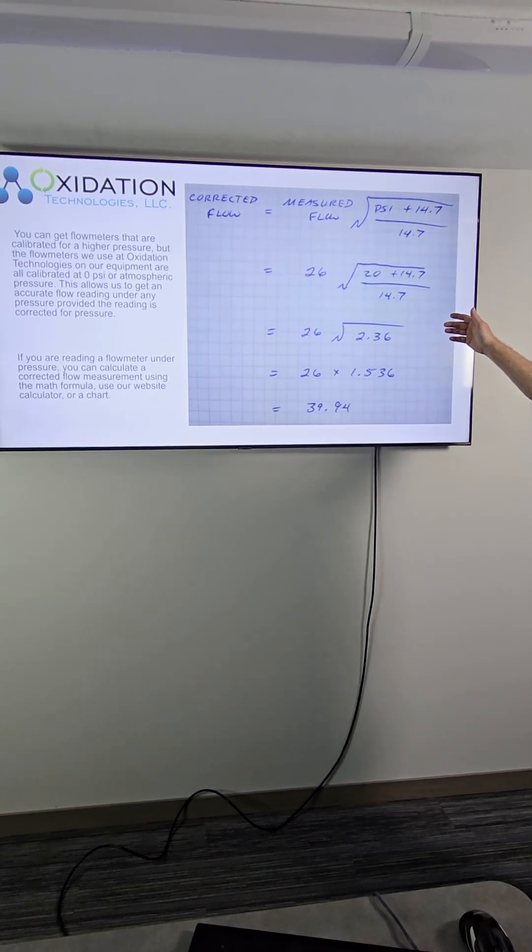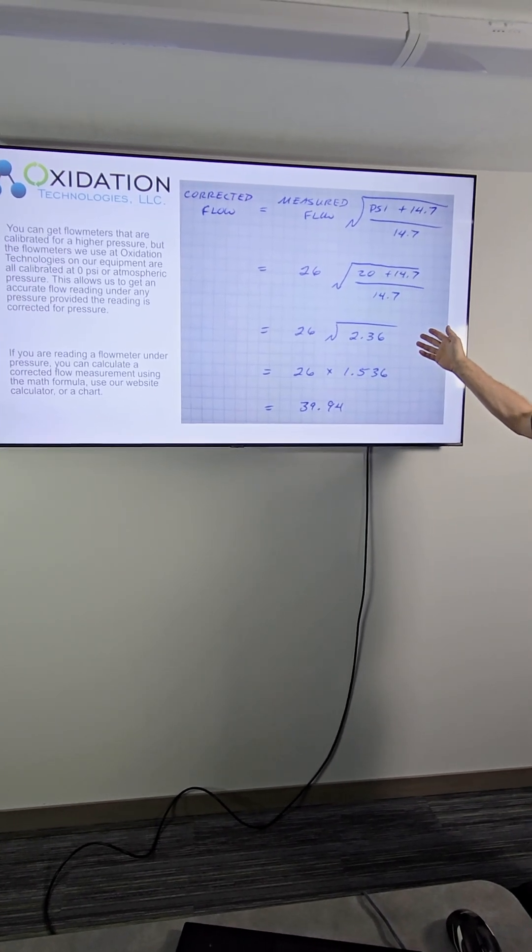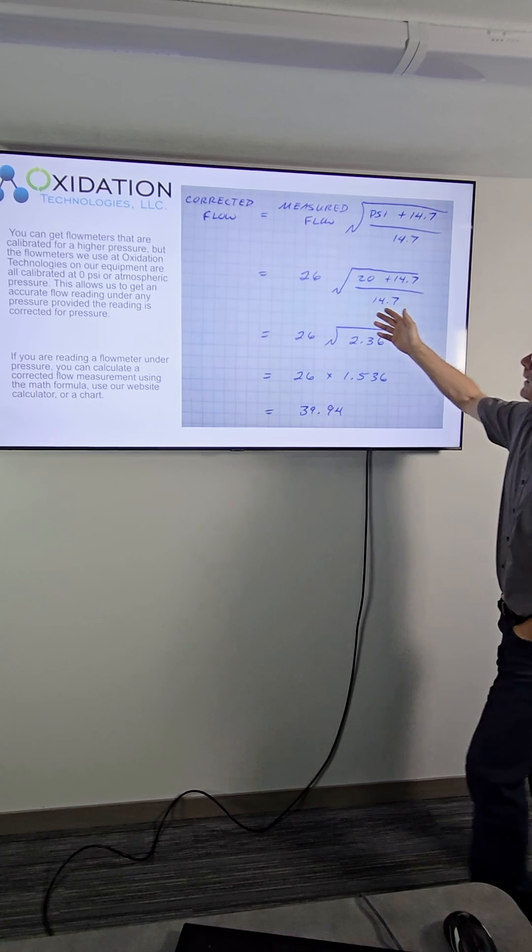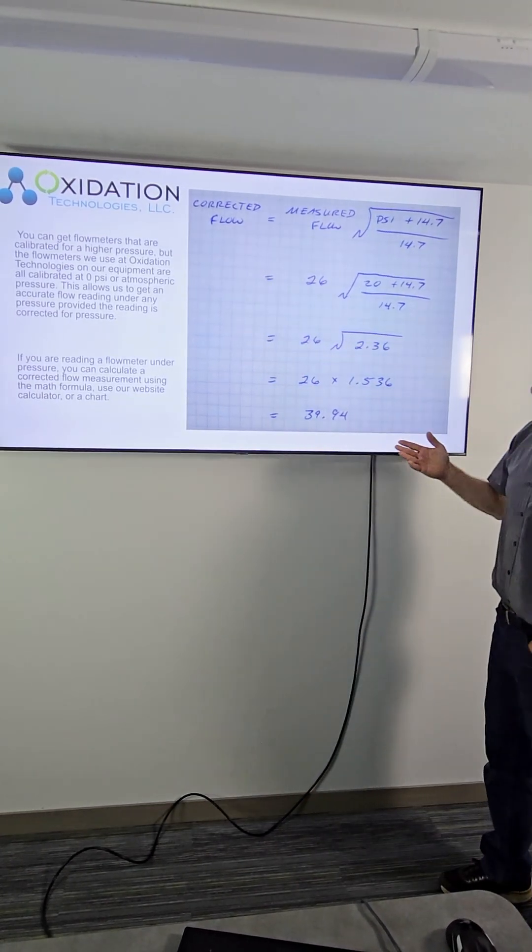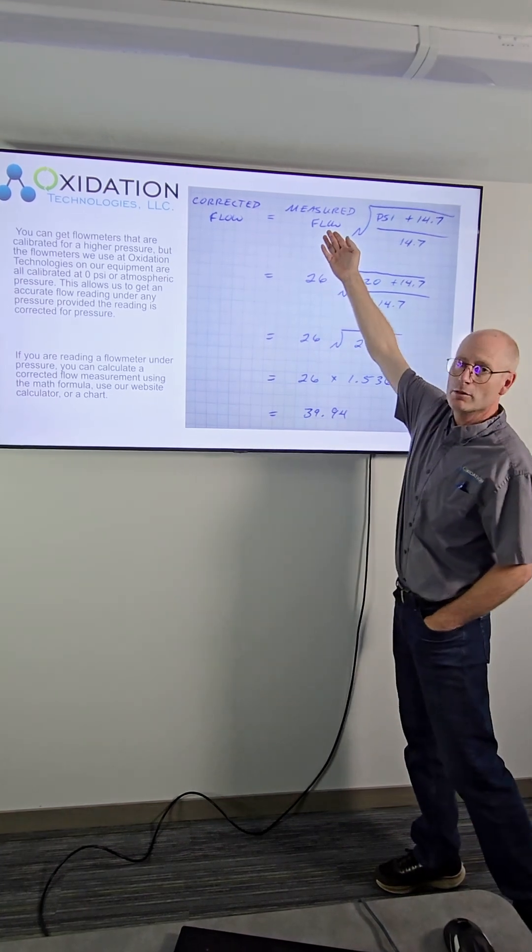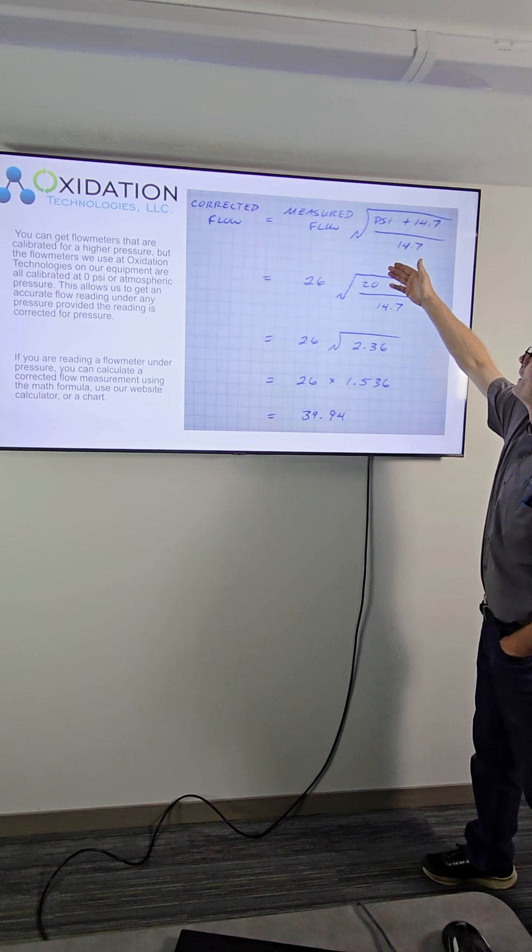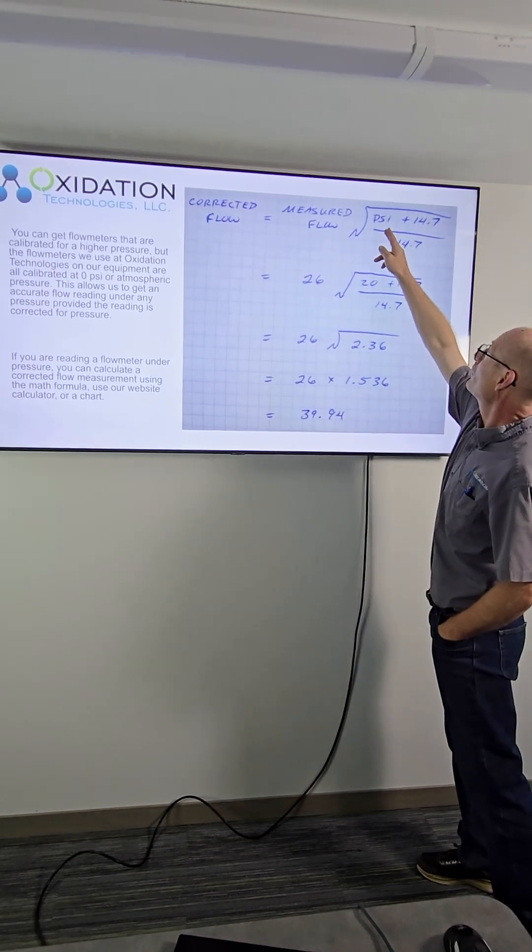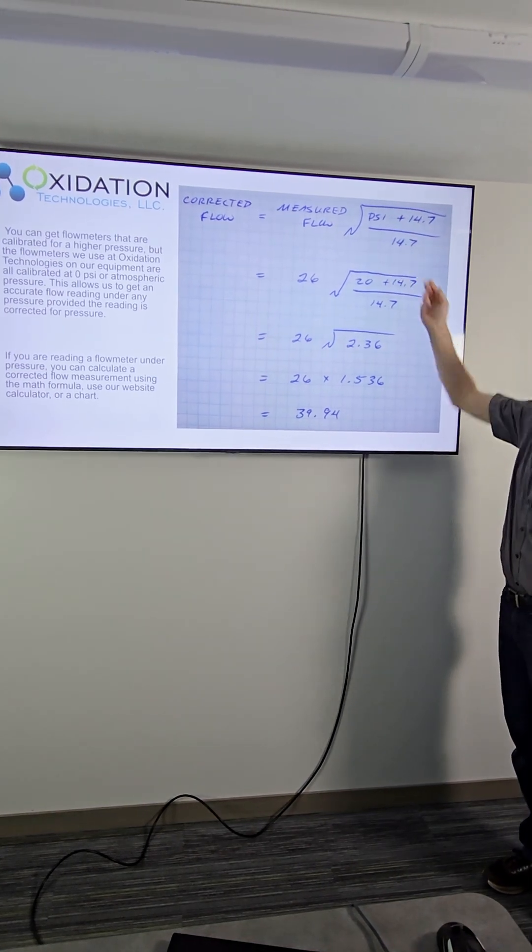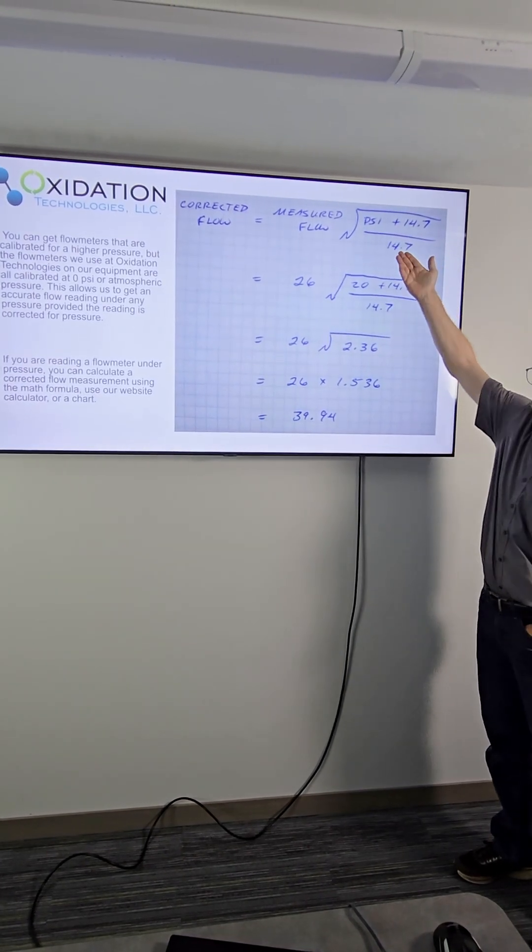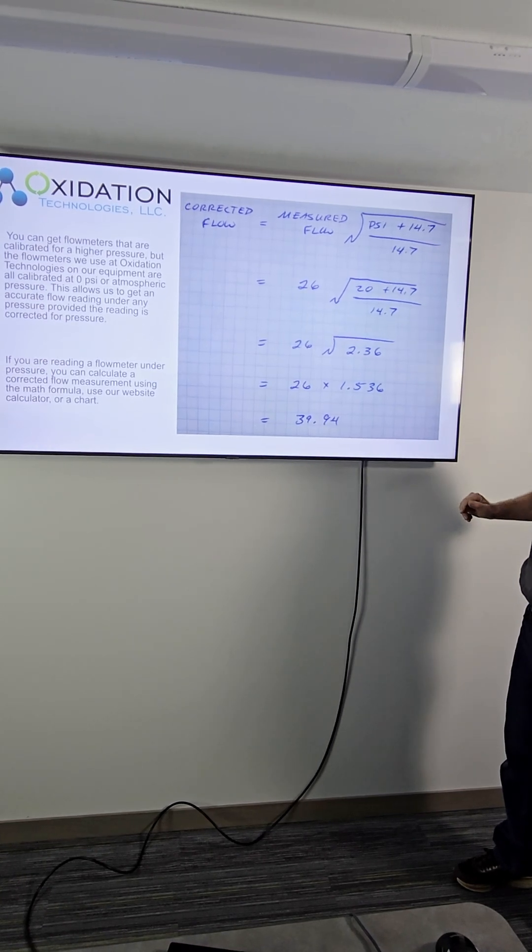So the equation that you use to correct for pressure, you can either do it longhand. There are calculators available as well. But the corrected flow, the actual flow, is going to equal whatever you measure times the square root of the psi plus 14.7 all divided by 14.7. 14.7 is the pressure of one atmosphere of pressure.